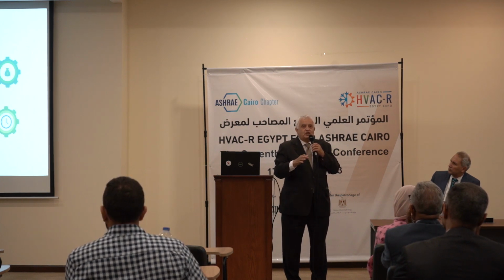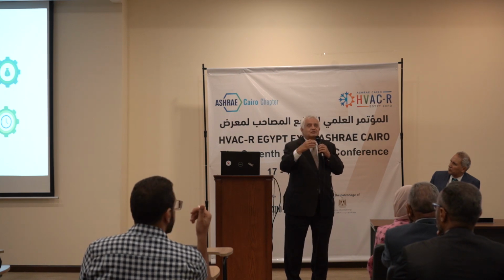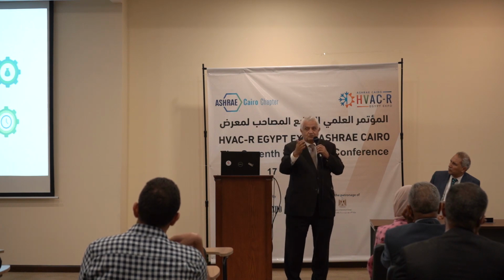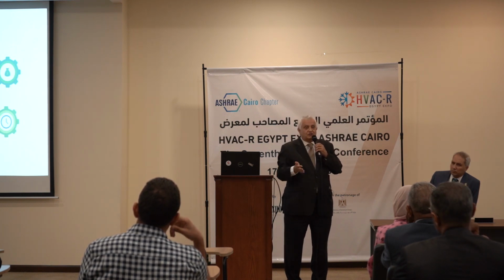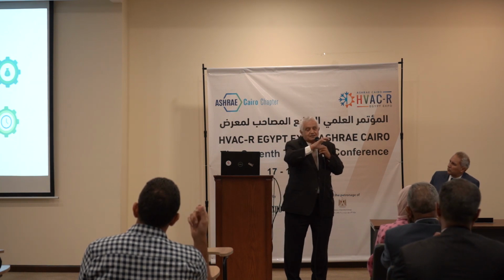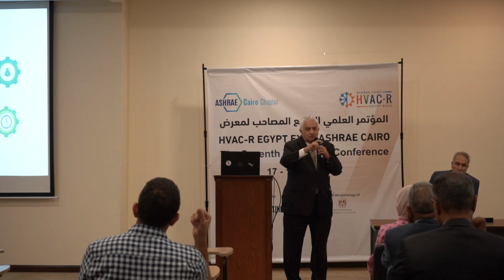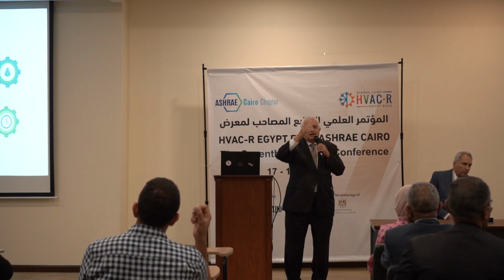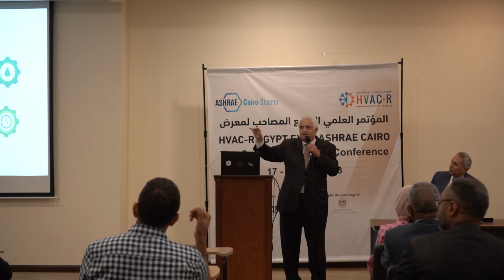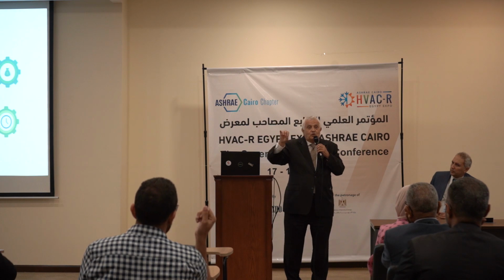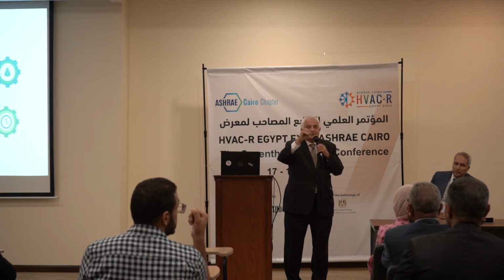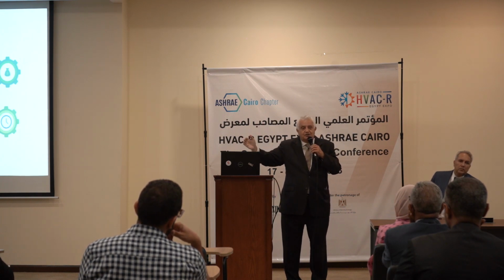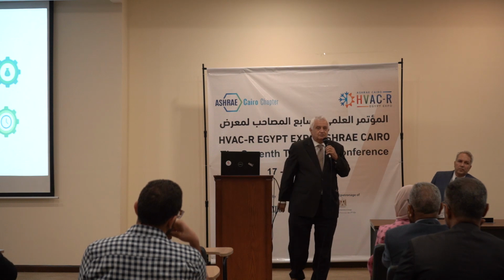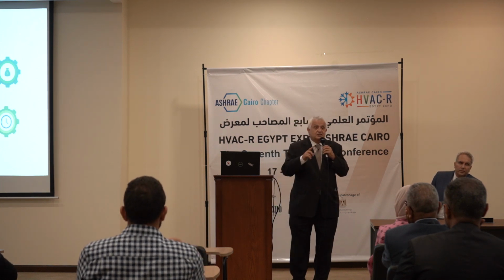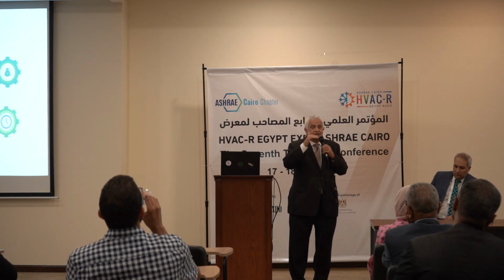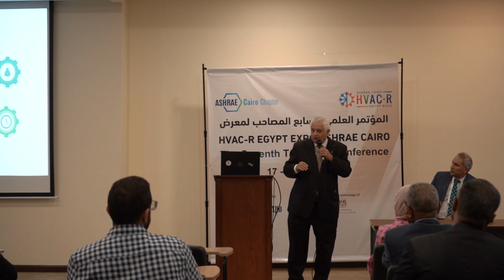By definition, a unit such as an IEC-H unit will be more expensive than a DX machine because it has more equipment and it's not produced on a mass production range like a DX machine. So he made this program where he would put the capital cost, which is more expensive for an IEC machine, and then see the operating cost over 15 years. And with the discount method, he calculates the price of the machine today, after 15 years of running the machine, the one that costs less is a better machine, as long as the efficiency is higher and the capacity is as good as or higher than that of the other one. And this is what we are going to prove.